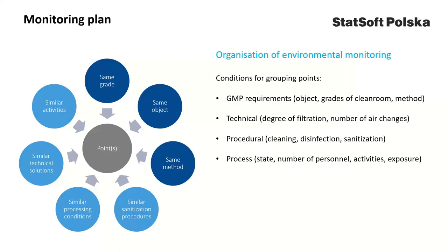For trending purposes, points can be grouped. The grouping scheme should be pre-established. It should be noted that the way the points are grouped is important to have a reliable picture of the state of the manufacturing environment. For example, microbiological levels can vary from one room to another, even having the same cleanliness grade, depending on the technical solutions used, contamination control procedures implemented, or process conditions. Also, the impact of potential limit breaches on product quality depends on the criticality of the technological operation conducted in a given room.